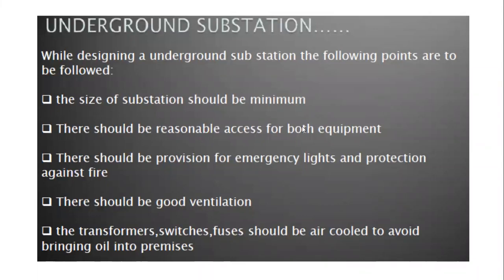There should be reasonable access for both the equipment and personnel, and there should be provision for emergency lights and protection against fire. If any fault occurs in this underground substation, identifying it is also difficult. For that reason we give high protection schemes for underground substations. There should also be good ventilation, so while designing this type of substation we provide good ventilation.